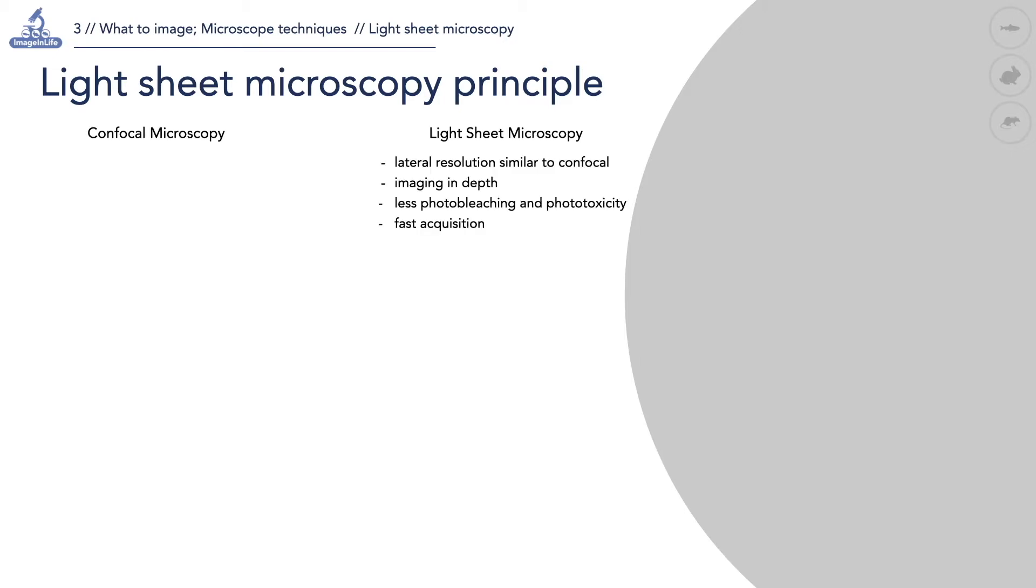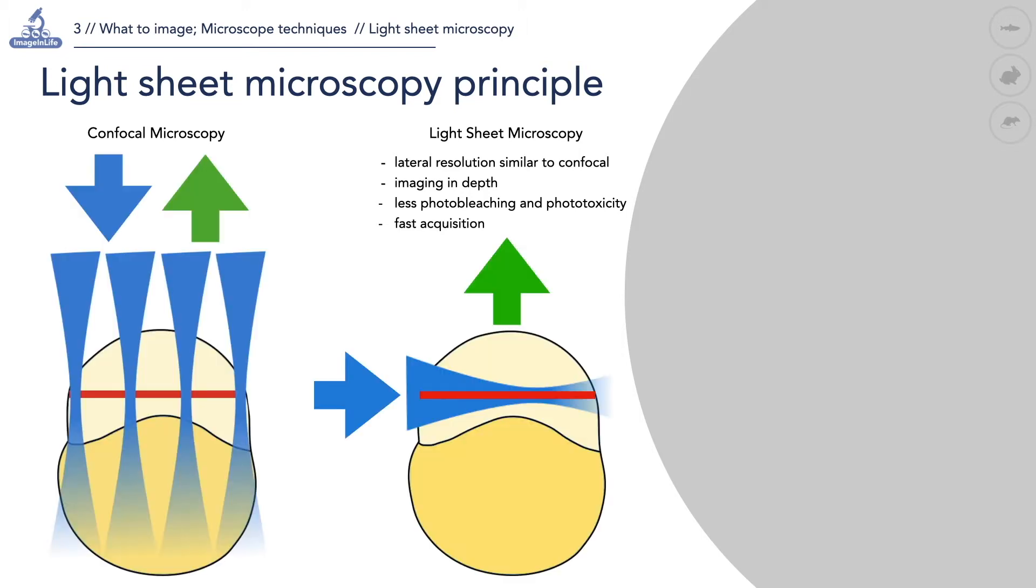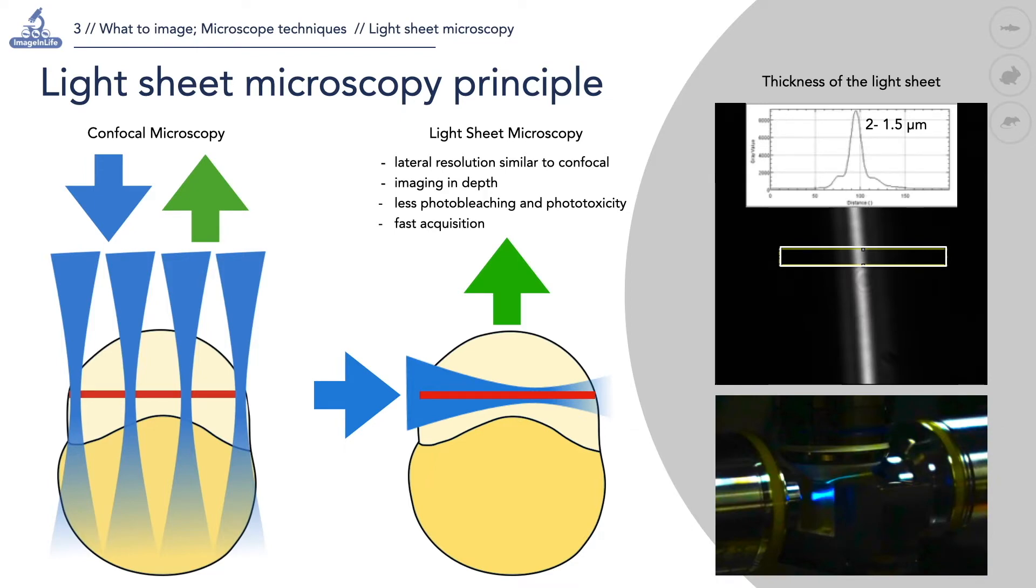Light sheet microscopy has a spatial resolution similar to confocal microscopy and also offers the possibility to image the sample in depth. With this technique the sample is illuminated in the region of the thin layer of light, in contrary to confocal microscopy where the excitation light travels through all the thickness of the sample. Light sheet microscopy leads to less photo damage for the sample than confocal microscopy. The thickness of the light sheet is about 1.5 micrometers. The light sheet can be adjusted depending on the requirements in terms of lateral and axial resolution.